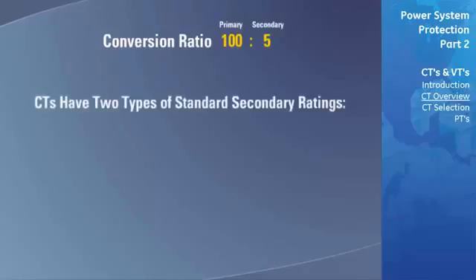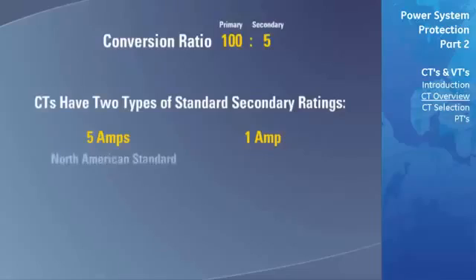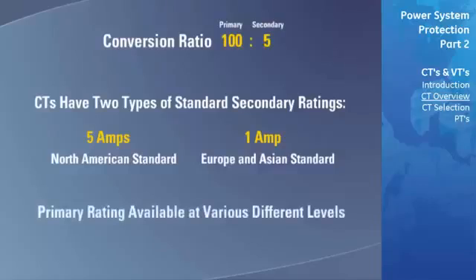CTs have two types of secondary ratings: 5 amps and 1 amp respectively. 5 amps is typically the North American standard, while 1 amp is used in Europe and Asia. CT ratios are available in various different levels, for example, 100, 150, 200, etc.